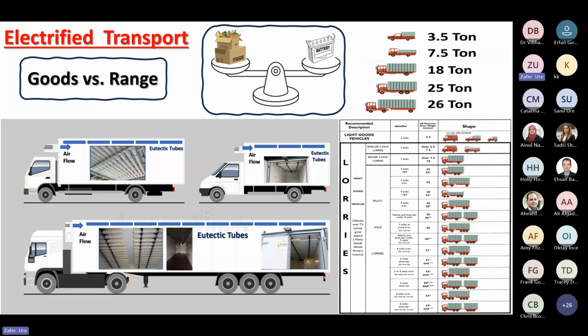Whether you balance the battery or the thermal storage, you find there are limits, as you can see on the right-hand side: 3.5, 7.5, 18, and maximum 26 tons on delivery lorries. As soon as you remove the engine-driven mechanical refrigeration and try to drive that refrigeration with batteries, now we have a problem.